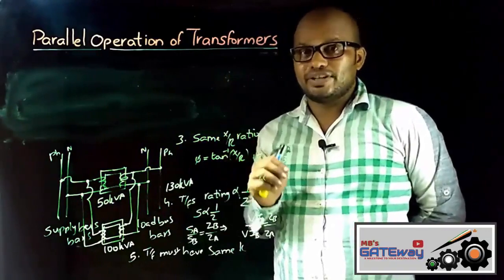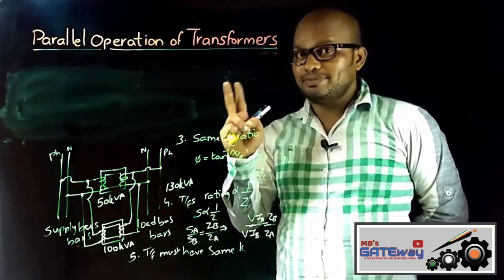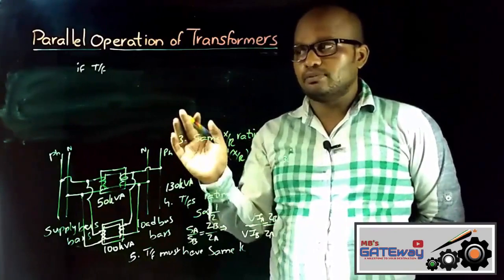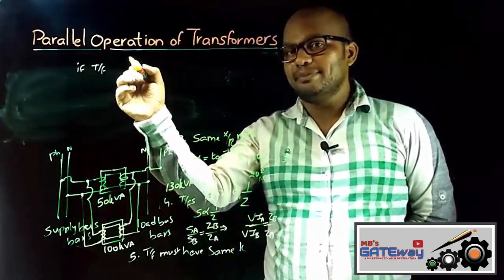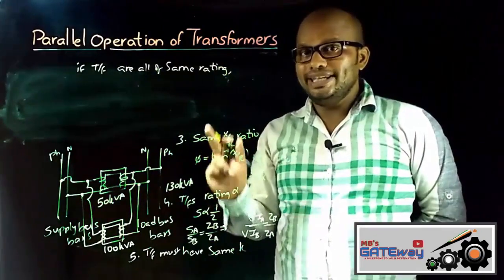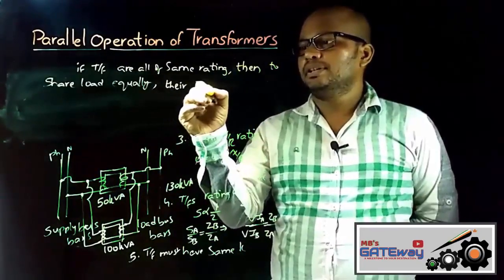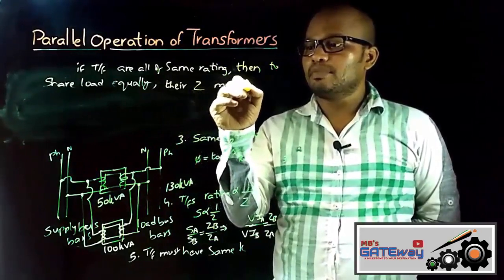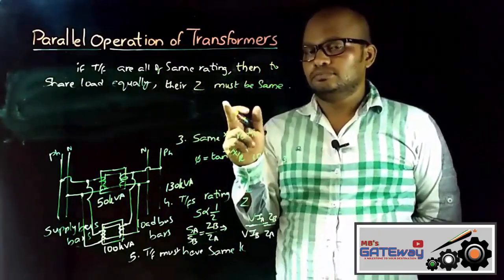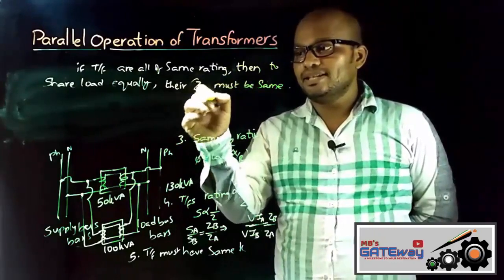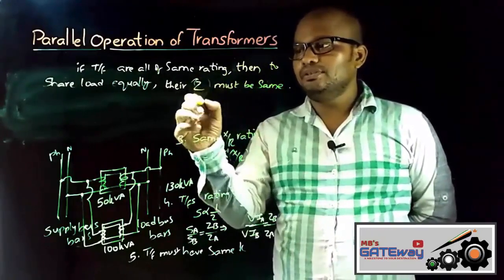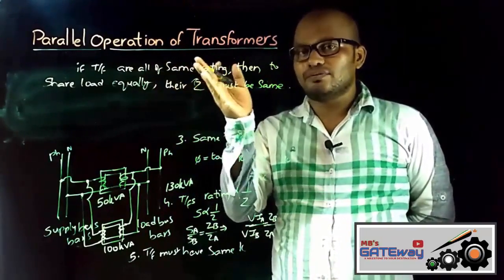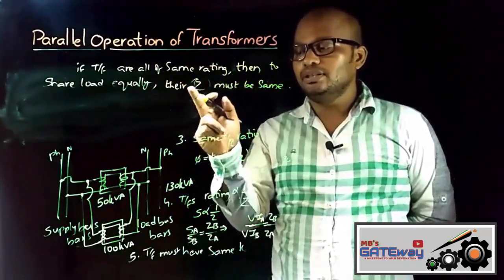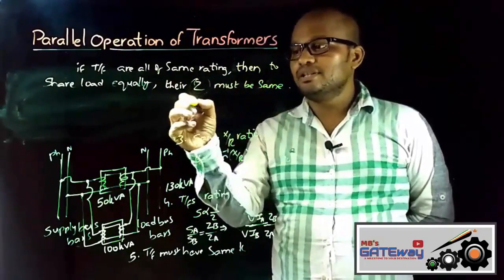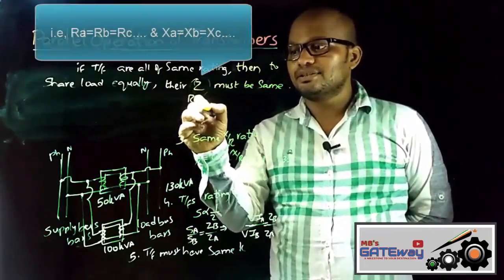Here in parallel operation of transformers, there are two important points that must be discussed. That is, if transformers have the same rating, then to share the load in equal proportion, their impedances must be the same. And here you must keep in mind that Z is not a numerical value. If transformers are of the same rating, then to share the load equally, their impedances must be the same, meaning all the transformers' resistances and reactances must be the same.